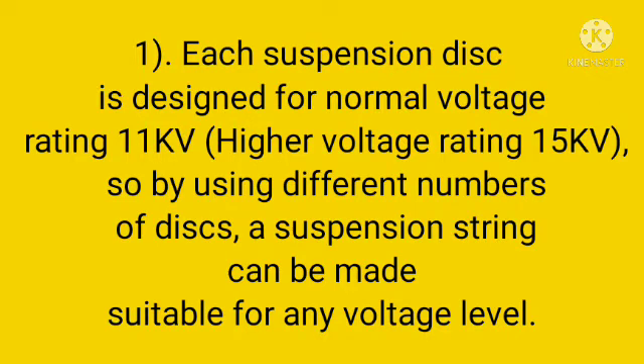Advantages of suspension insulators: each suspension disc is designed for a normal voltage rating of 11kV or a higher voltage rating of 15kV. So by using different numbers of discs, a suspension string can be made suitable for any voltage level.